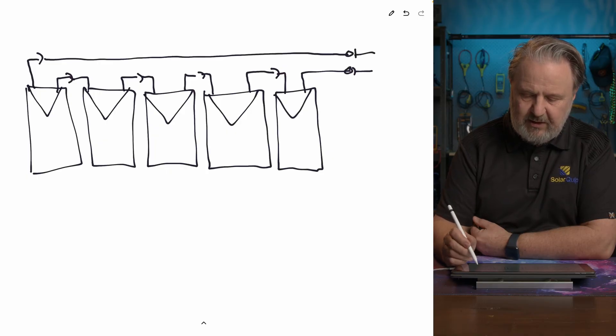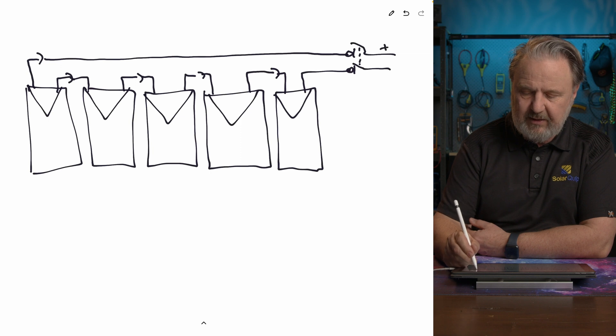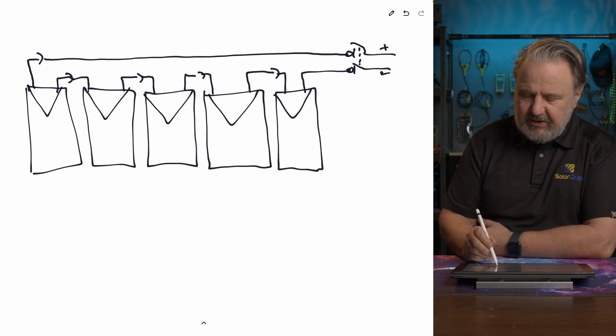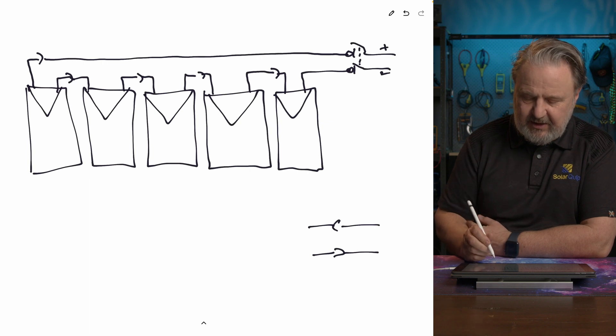In newer systems, since the new standard for PV arrays ASNZS 5033 the 2021 edition, we introduced a new feature called the disconnection point. The disconnection point allows you to not have a load break disconnector but just use the plug and sockets at the end of the string as the point of disconnection. There are two types: a load break disconnector — ganged so both poles disconnect at the same time — or simply another plug and socket, which is known as a disconnection point or DP for short.